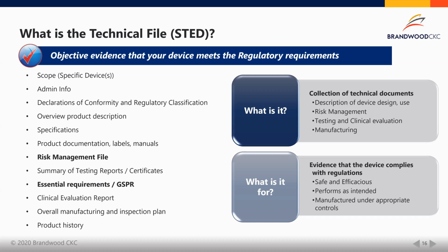Another one is the clinical evidence, so the clinical evaluation report is another big component. Each device, no matter what classification, will need to have a tech file. The level of detail within that will depend on the classification. The riskier the device, the more data you need.